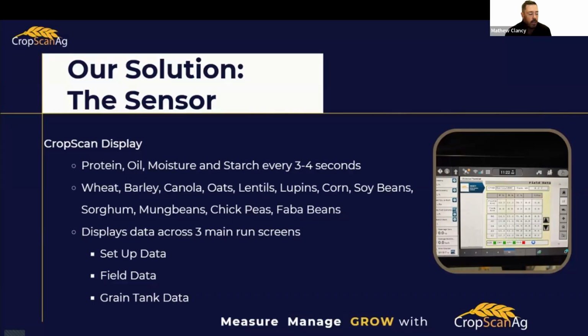Some calibrations will perform better than others. We are seeing more feed barley being produced, and the rougher it's produced, the wilder the results in the barley can be, due to the poor sample presentation to the sensor. The sensors are designed to measure good seeds. So wheat and canola, even with a bit of admixture in there, is going to give you a pretty good result. But with barley, if you've got really long horns on it, it can produce odd results, because all it's measuring is the light transmitted through the seed. It wants to measure the seed, not the horns. So a little bit of a warning there.